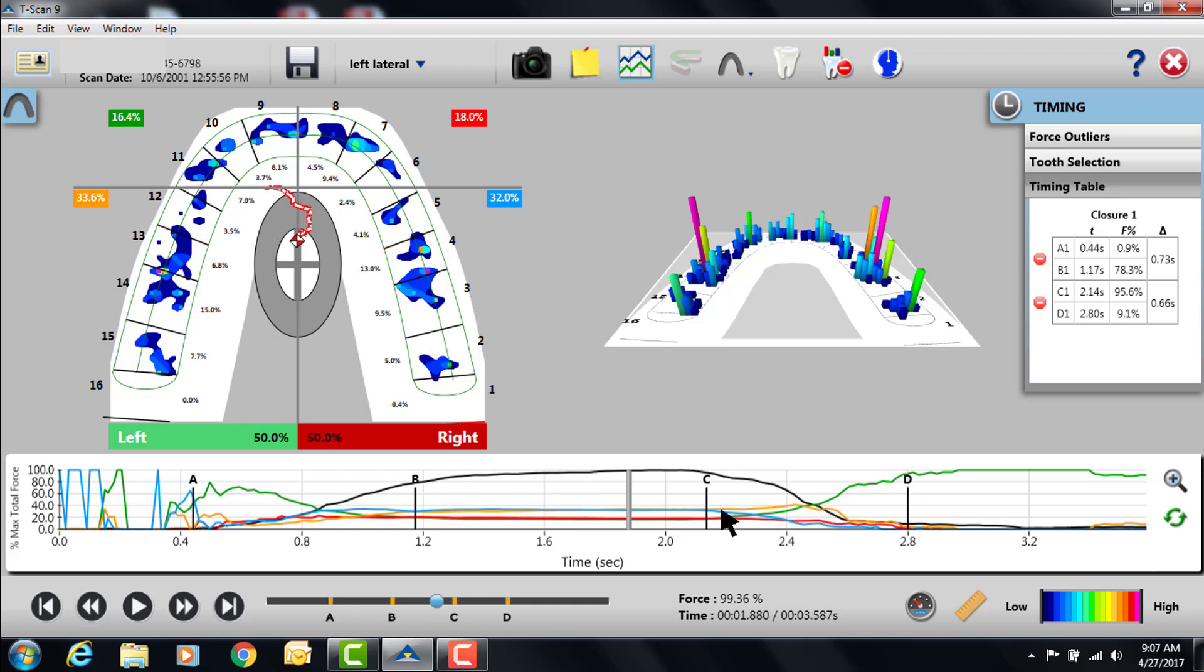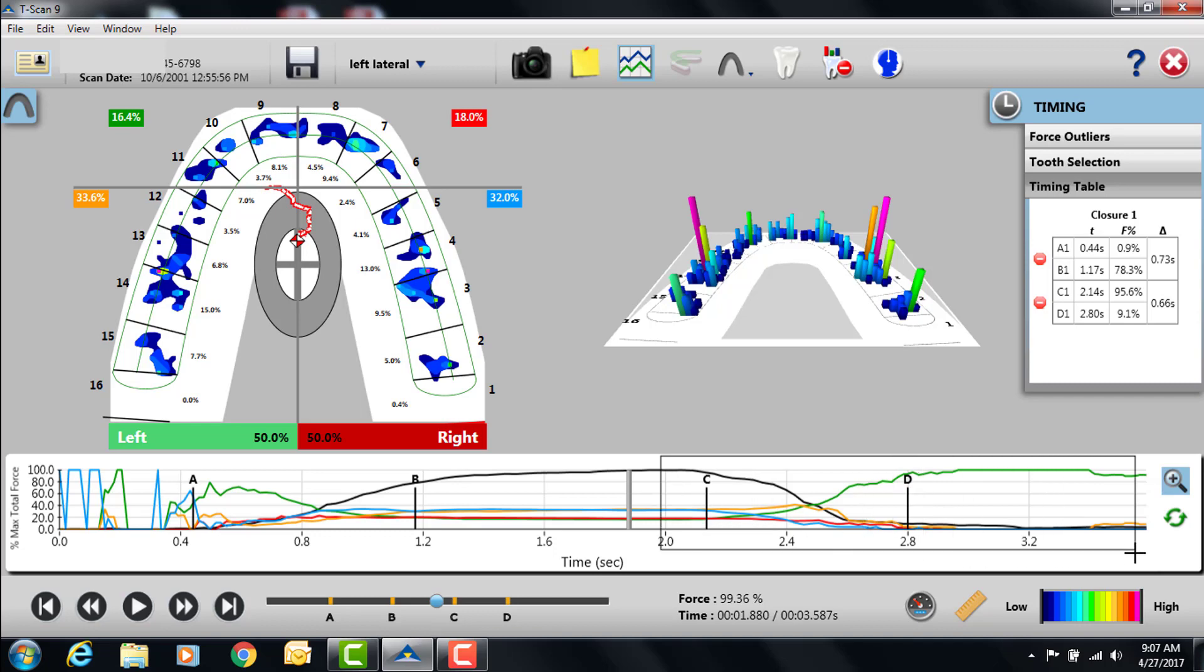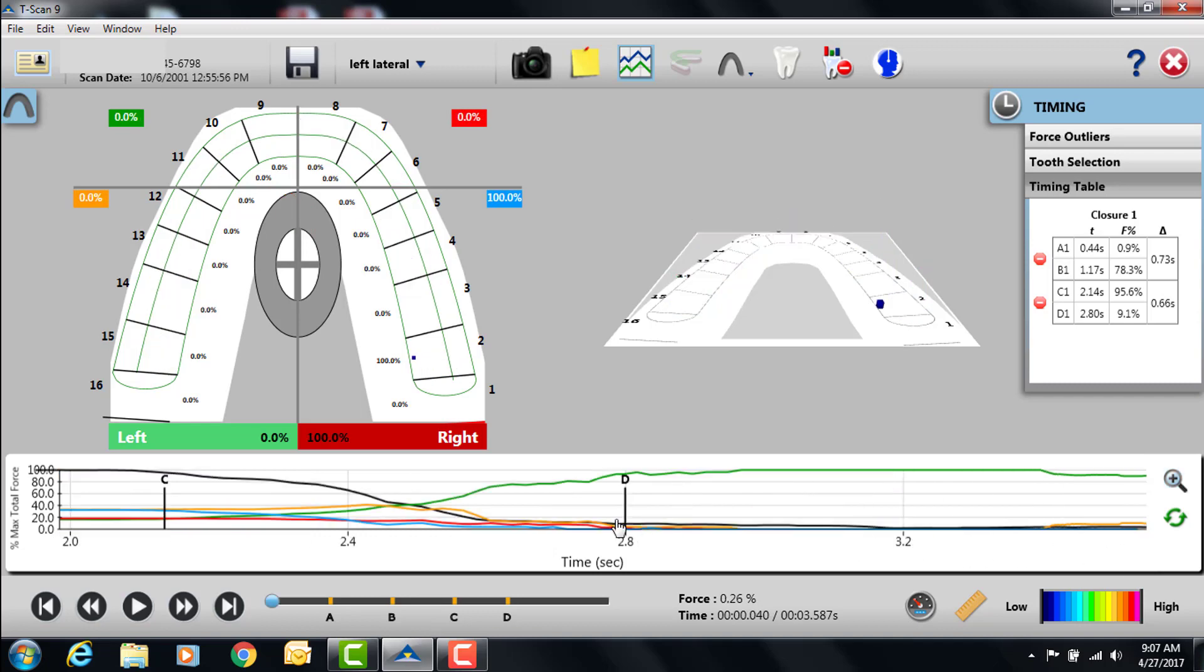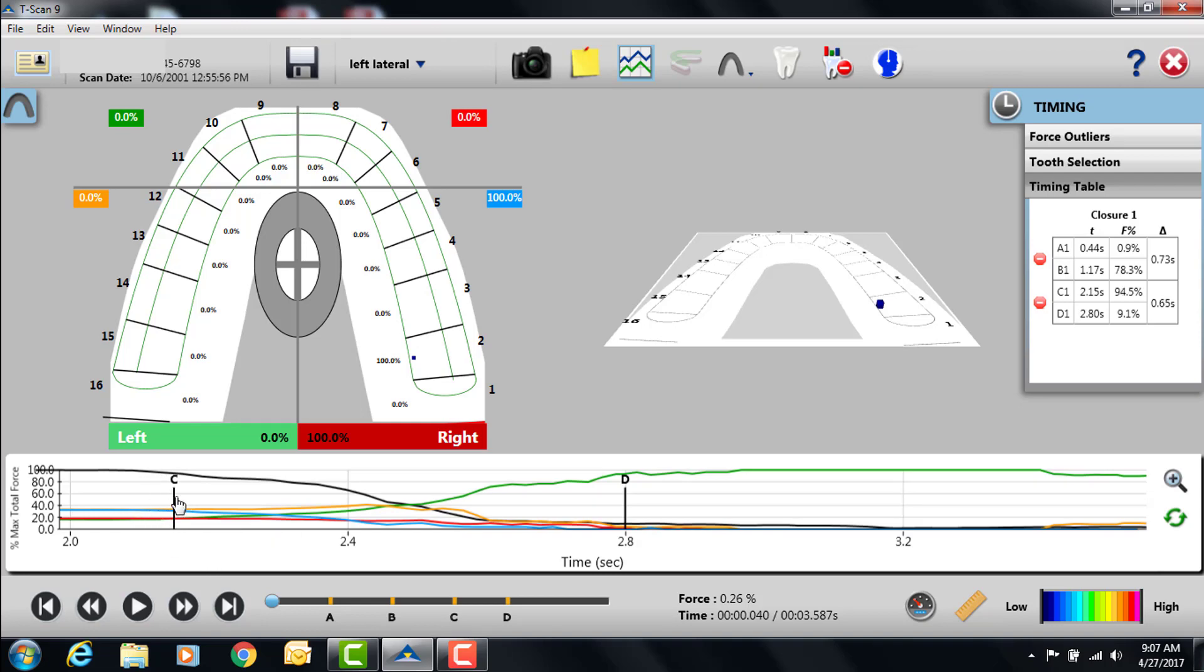Alright, and so when we want to set the C line, you want to move the C line to the point where all the colors start to move away from each other, and you can see it's actually in a good spot right now, which is a testament to the software. And I can zoom in here, clicking the zoom feature, just do a square around the C to D area, and you can really see the C line is exactly where it needs to be, so the computer as normal will do a great job of this. But if it wasn't, you can move it slightly to the left or right of that location.